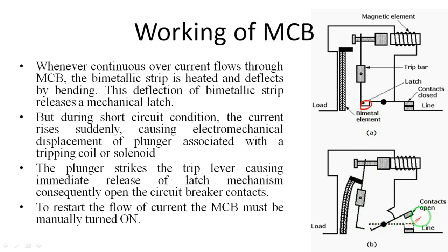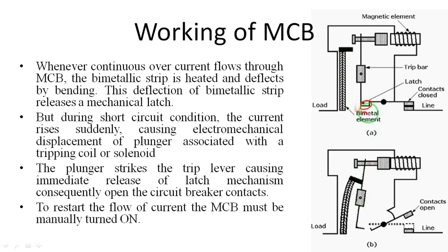Due to this mechanism, the circuit breaker contacts automatically open. To summarize: when overcurrent passes through the line, the bimetallic strip heats and bends. The plunger strikes the trip lever, which opens the latch. The latch mechanism is connected to the contacts, so the contacts open. If you want to restore current flow, you have to manually turn it on.